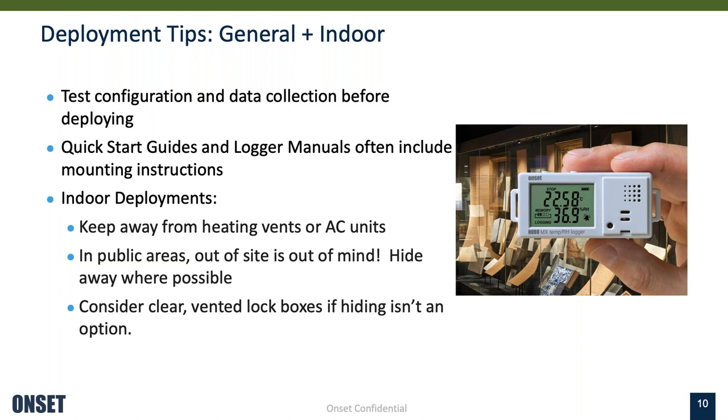Just a couple more points for indoor deployments. These are devices that would be used in, perhaps, a manufacturing facility or an office building, where you have a controlled, non-condensing environment. If you are looking to get a temperature profile of a particular area, you want to make sure that you keep away from heating vents or AC units, so you don't want those directly next to, above, or below the logger. Because you're so close, you may not get accurate data of what the human experience might be in that room. When the heat turns on, it's going to influence that logger quite a bit, and the same thing if the AC runs.